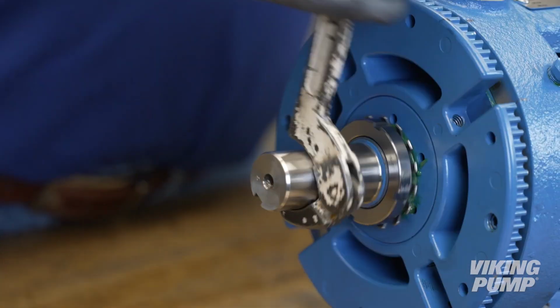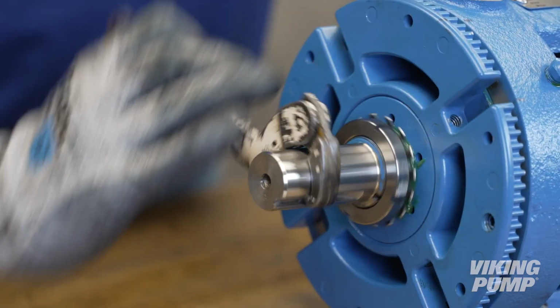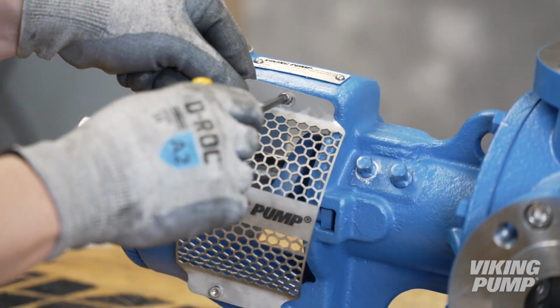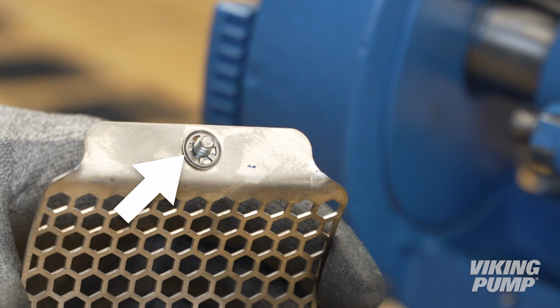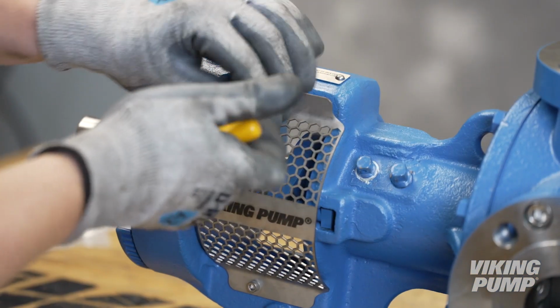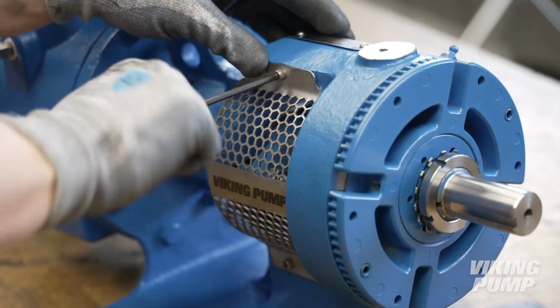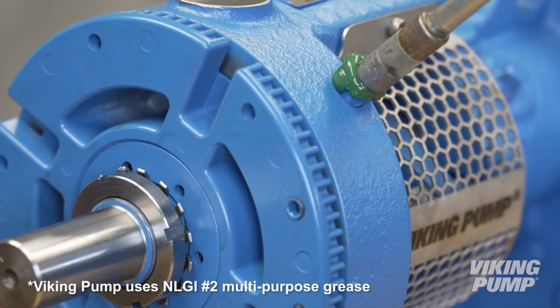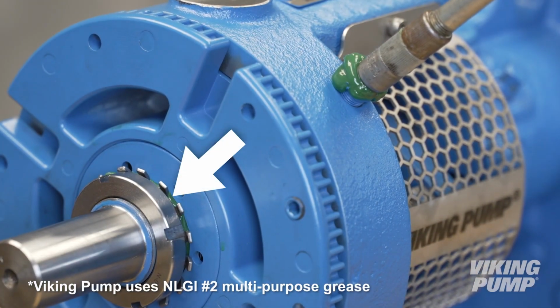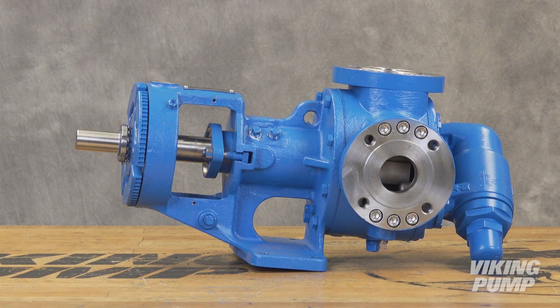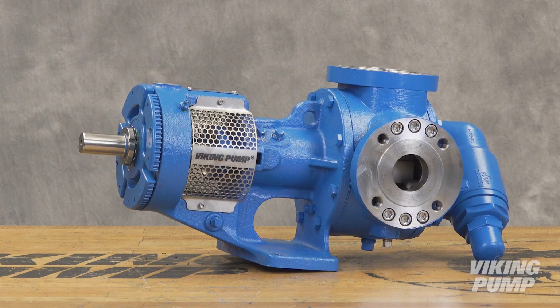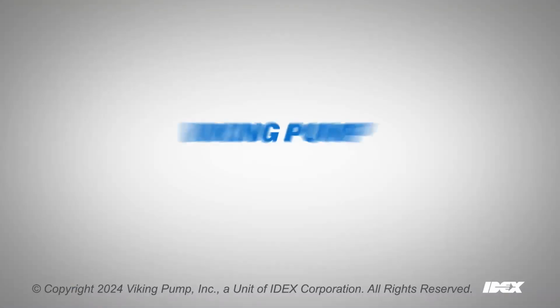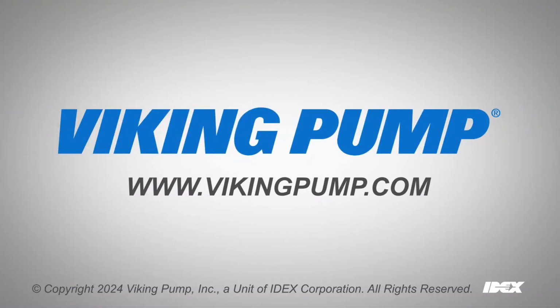Turn the shaft to ensure the pump turns freely. Reinstall the window guards. Ensure that the retaining washer is placed between the guard and bracket faces. Finally, grease the bearing housing until grease begins to appear around the lock washer. Your pump has new packing and is ready to be put back into service. For more information or to view other service videos, please visit our website at vikingpump.com.